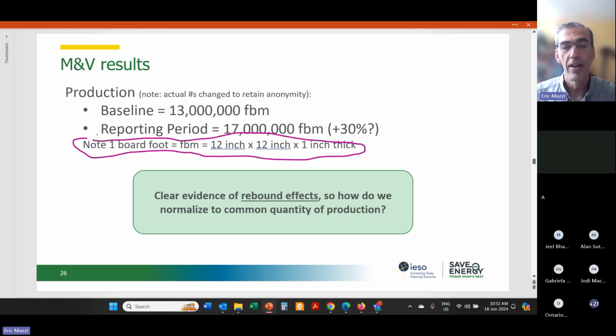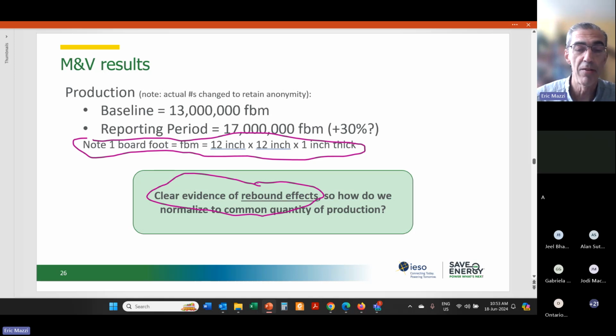So again, it's a batch process. And due to the improvements in this control system, it was actually very good news for the owner that they could dry 30% more lumber every 12 months because of this retrofit. Now, that introduced some tricky issues in the M&V, though, because that's what's called a rebound effect, right? I can talk more during the Q&A, but the long and short is a rebound effect is where the energy efficiency measure leads to an increase in the activity. In this case, the activity is the production of dried lumber. So that technology itself is what enabled and caused an increase in production, which actually was a good thing, because in manufacturing, anytime you can squeeze more production out of your existing equipment, you're a hero, right? That has good economic value.